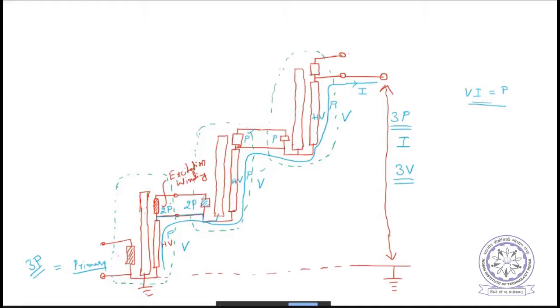And now this cascading of the transformer under nominal loads, meaning for which it is designed, is okay, no problem. Almost every high voltage lab will be having this cascaded transformer set. But in some cases, for testing cables, etc., these cascaded sets are not so recommended. For testing transformers and other small equipment, the cascaded transformer set is good.